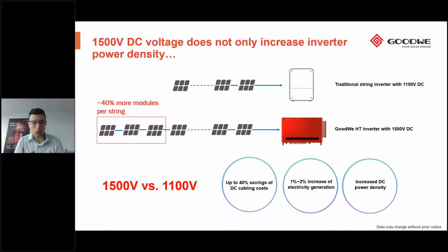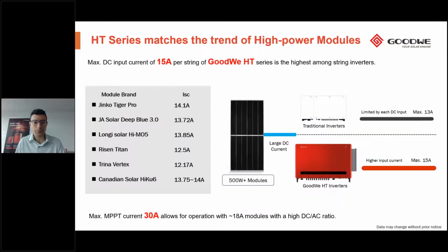So this is a major advantage also in terms of overall capex, overall investment costs, but also helps generating higher electricity. And we made some side-by-side comparison in some ground mount installations of the 1100 volt and 1500 volt systems, and we do see that the 1500 volt systems have a higher electricity generation of 1 to 2%. This is due, for the technical people among you, to the higher voltage allowing operation with lower currents, and this means lower losses and therefore higher electricity generation. Also, the inverters are able to be more efficient with this voltage technology. And next to that, the additional benefit is the increased DC power density, and this is especially on the panel side, and I think Jason from LONGi will also be sharing more about this trend later.